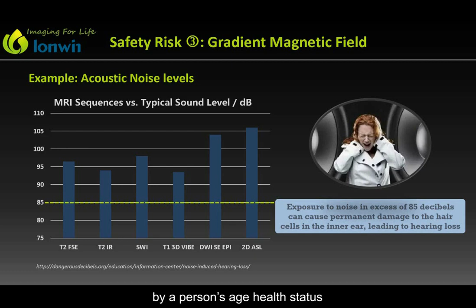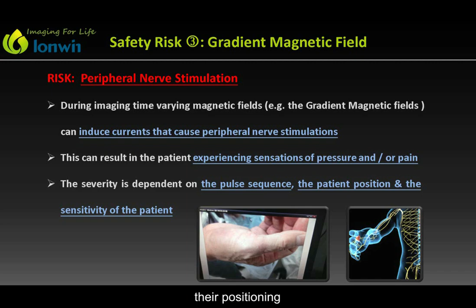Peripheral nerve stimulation is another risk of MRI resulting from time-varying fields such as the gradient magnetic field. It should be noted that peripheral nerve stimulation generally results in discomfort rather than long-term injury. Currents can be induced in a patient's peripheral nerve fibers, possibly causing sensations of pressure or pain, or may result in twitching sensations. This can be quite uncomfortable for the patient. The degree of sensation is dependent on the sensitivity of the patient, their positioning, and the types of images being required.